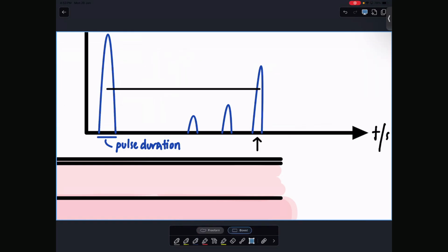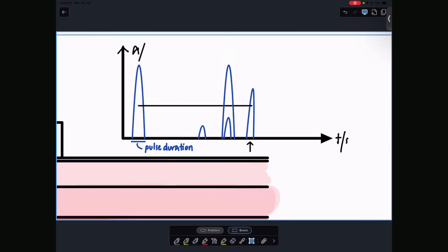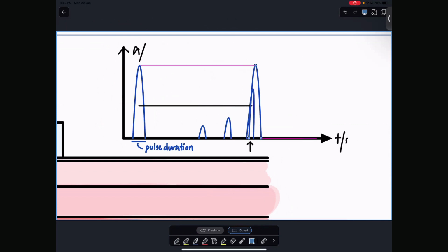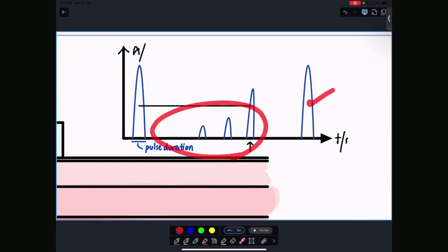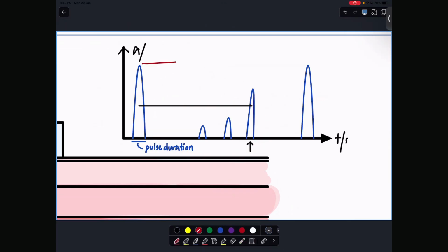But let's say our second pulse I release here. Would that be a good idea? Remember the first pulse I sent? I send the second pulse here. Is that a good thing? No, because isn't my incoming pulse and the reflected pulse now overlapping each other? So where do you think would be a good place to put this pulse? Yeah, somewhere here, so that everything comes back first. Now let's send it again. Do you get my point? This whole thing that you see here is known as the pulse interval.